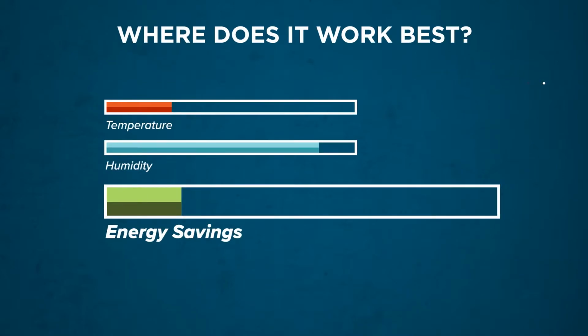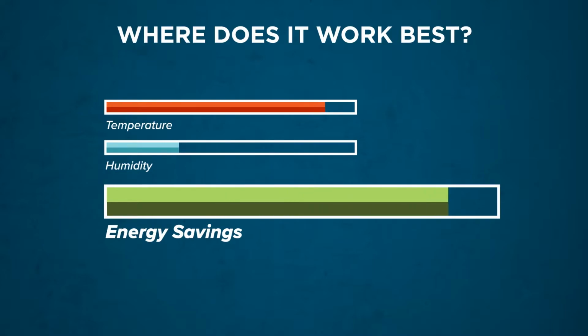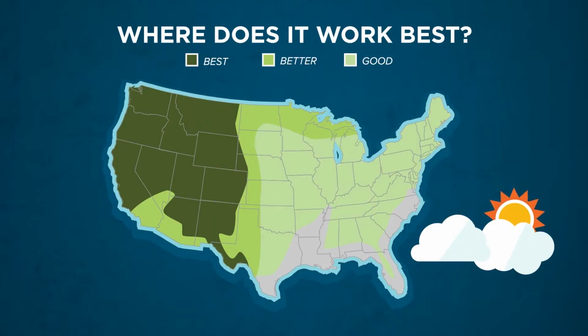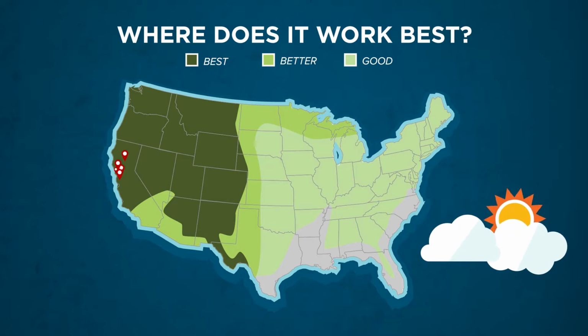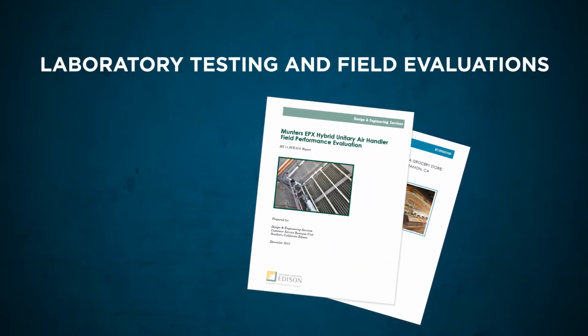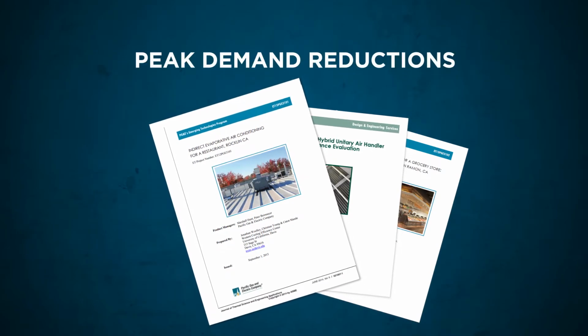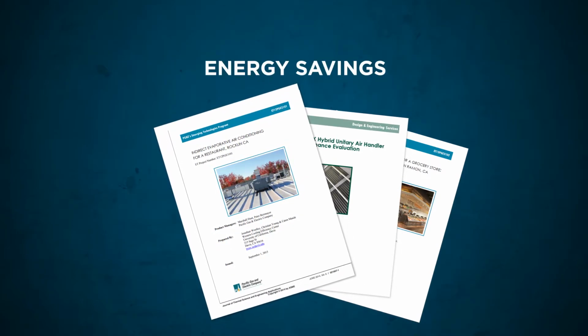Munters EPX is effective in a range of climates and applications, but the energy savings achieved increases as outdoor temperature increases and humidity decreases. So the EPX is particularly well suited for hot and dry climates. Most of the western United States is suitable for the EPX. Munters EPX units have been installed in locations such as Santa Clara, San Ramon, Richmond, Chico, San Francisco, Sacramento, Las Vegas, Albuquerque, and Tucson. Independent lab and field tests have verified the performance of the EPX and demonstrated both peak demand reductions and energy savings.